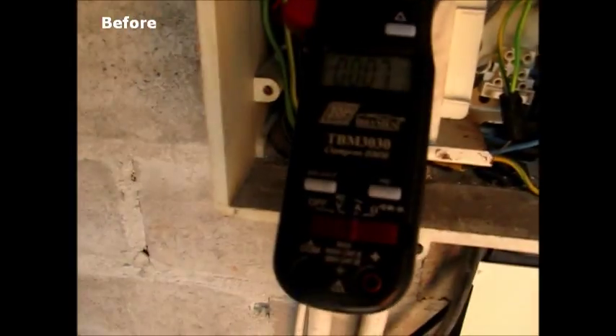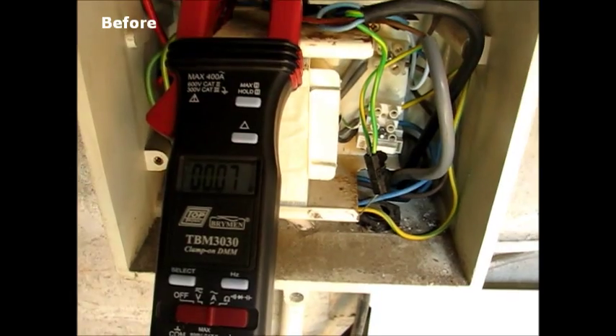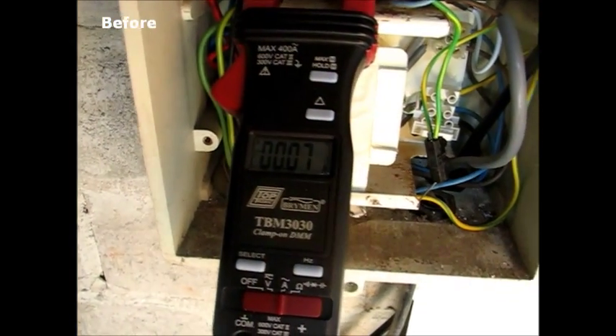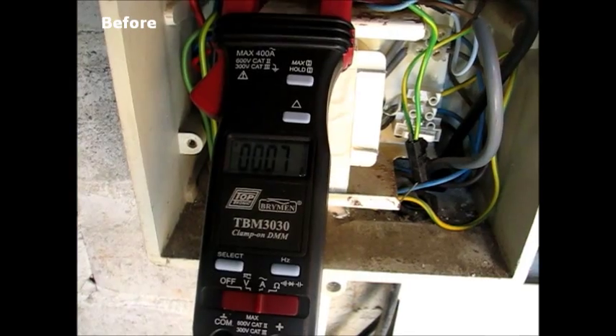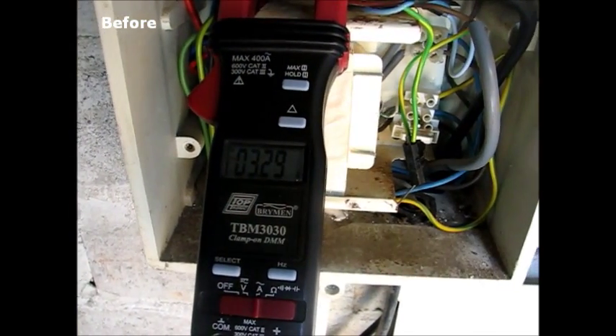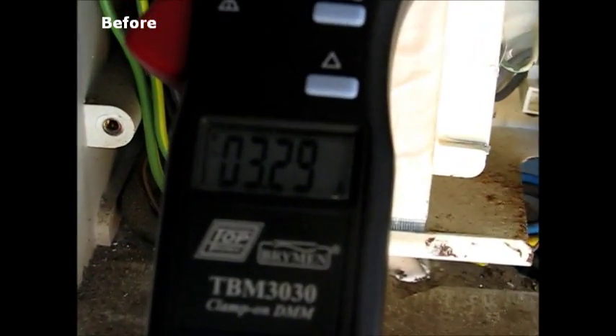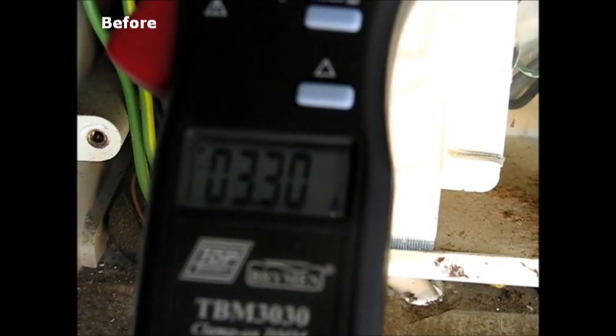The ammeter reading with the pump off is very nearly zero. We're activating the pump now. As can be noted, the reading has increased, going up to an average of 3.3 amps. This is the normal current drawn by the motor running on mains power.